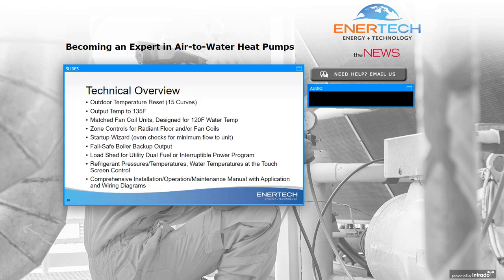All right, a little bit more on the technical side. We've talked about some of the features, but this is what you're going to want to know as you're installing this product. What do you have to plan for in the installation? One of the really nice features is the outdoor temperature reset with 15 curves. So you can choose the curve that makes the most sense for your climate. And as I mentioned earlier, the lower the water temperature we can use, the more efficient it is. So if we don't need 110 degree water running through the floor, we might want to try 85 degrees or even 80 degrees, depending upon the outdoor temperature.